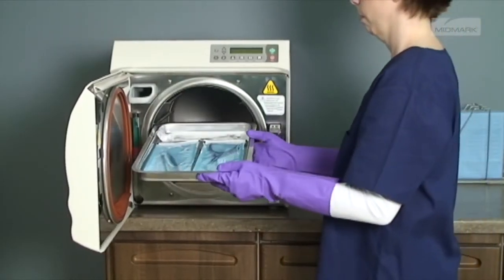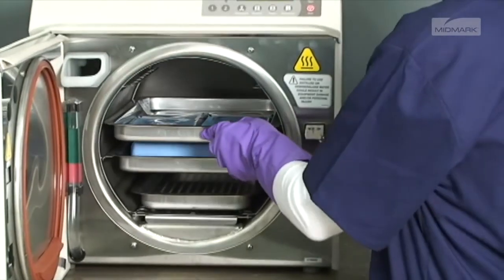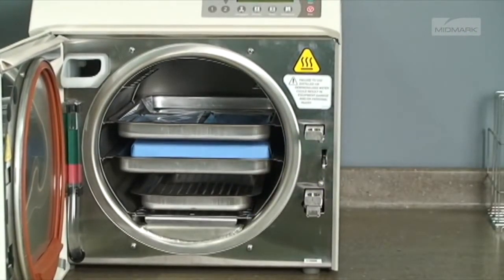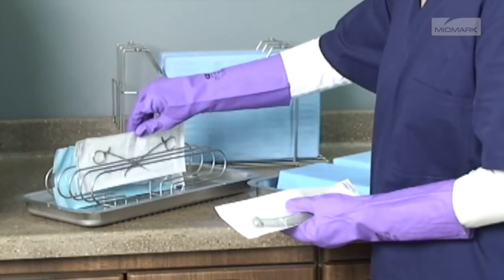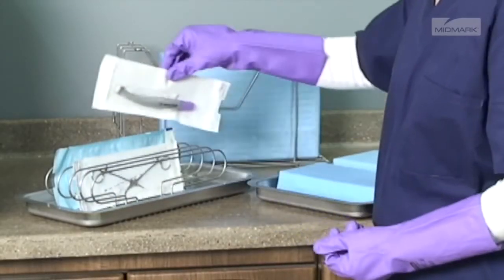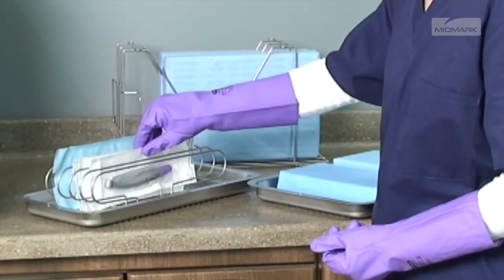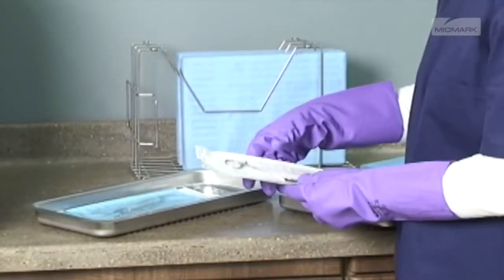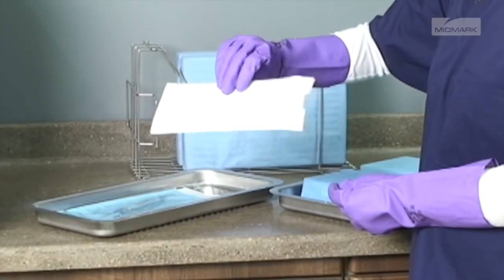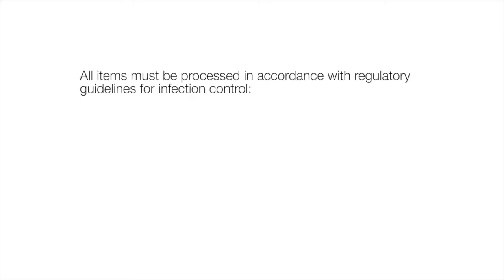Handpieces and instruments must be single-height loaded, not piled or stacked, to permit proper steam flow and penetration to the items. The preferred orientation for pouches is resting on their edge, best accomplished using the Midmark pouch rack accessory. If using the standard tray, pouches should be placed paper side down. All items must be processed in accordance with regulatory guidelines for infection control.